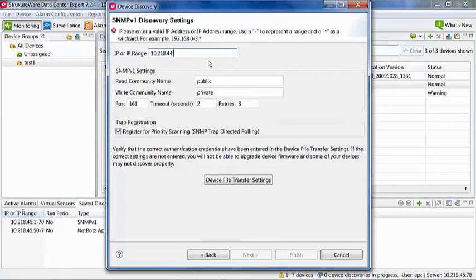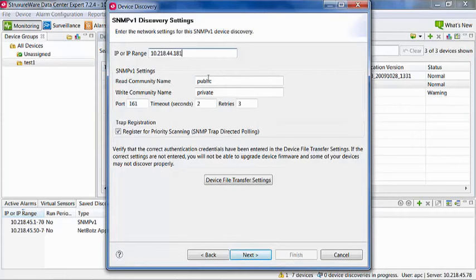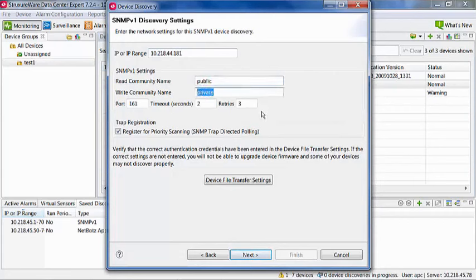Next, we need to add community names as configured in the devices to be discovered. These values should be noted on the devices themselves prior to attempting discovery. Only one set of community names can be used per discovery. If devices in a specific IP range have different community names, multiple discoveries must be made, each with different community names.